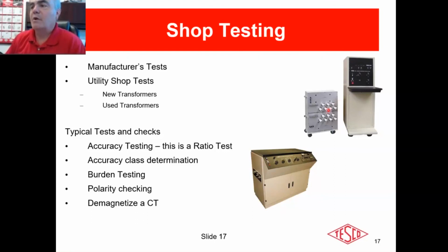This right here is a voltage test system, and it's a little easier to see because the precision transformer is right here and the loading transformer is right here. All right. These precision transformers are exceptionally accurate. This particular one goes up to 14,400. We also make one that goes up to 36,600 because that's the limit of what our metering customers really need.